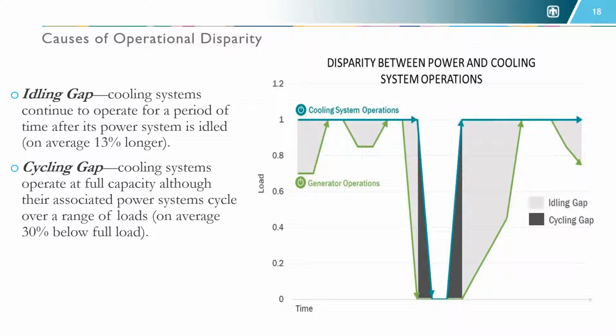But the important point is the cooling system, when it's on, it's on; when it's off, it's off. There's no following that load or cycling of the generator. That light gray area is what we call the cycling gap - the time when the generator is operating at something less than full capacity while the cooling system is operating at full capacity, creating a disparity between those two numbers.